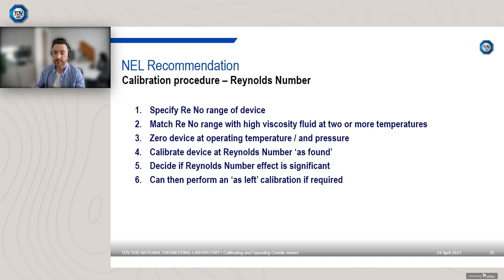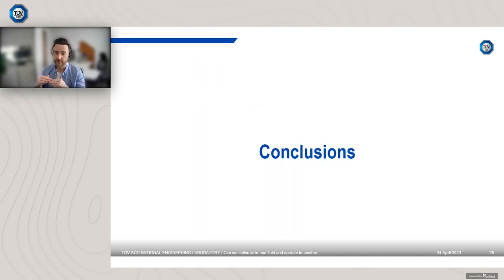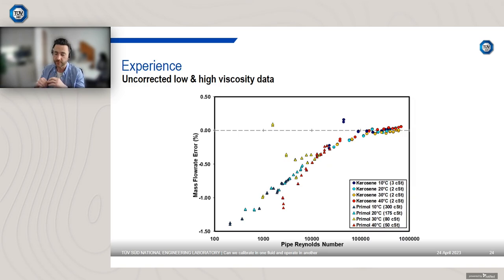We can then perform an as-left calibration if required. So if there's an offset outside of the Reynolds number effect, we can adjust it, move it up or down. And then we can also have a linear compensation. So I've not put that linear compensation through like I did for the pressure, but it certainly is possible. So you could have a linear compensation factor with respect to Reynolds number.